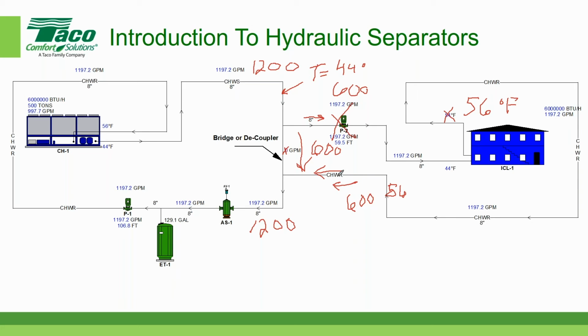Well, that 56 degrees is mixing with that 44, because remember what's going across the bridge is 44 degrees. We said that's 44 in this direction, 44 in that direction, but 56 is now combining with 44. And because the flows are half of what they were before, if you do the mix calculation out, you'll find that the temperature is going to be halfway between these two. So since the differential is 12, that's 6. So this water temperature is going to come back at 50 degrees Fahrenheit right here.